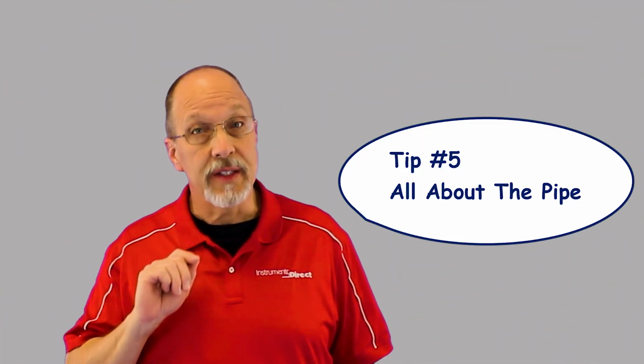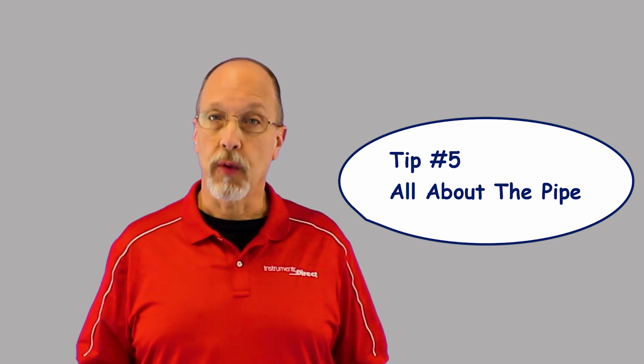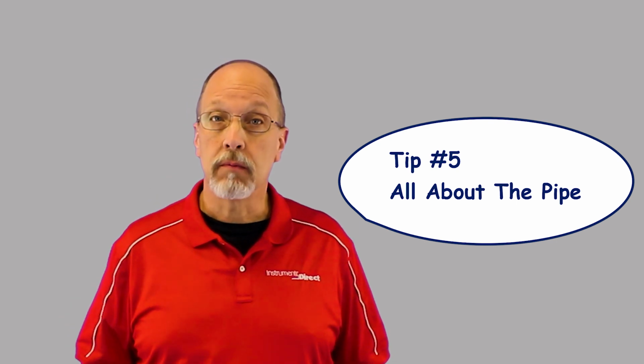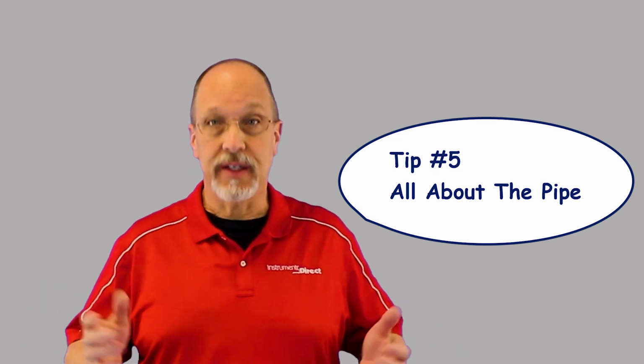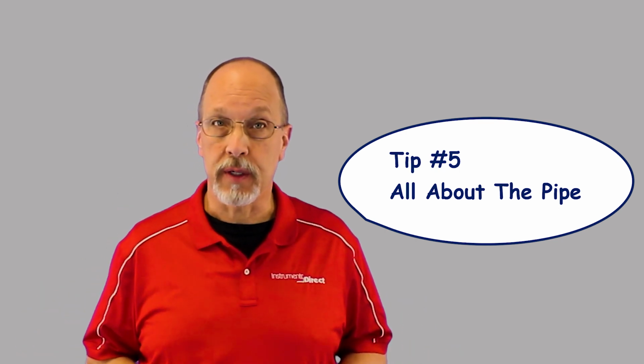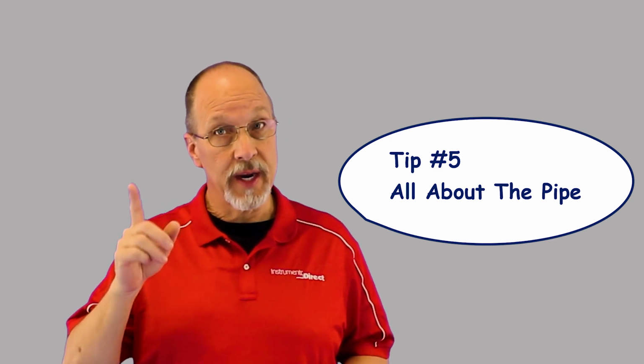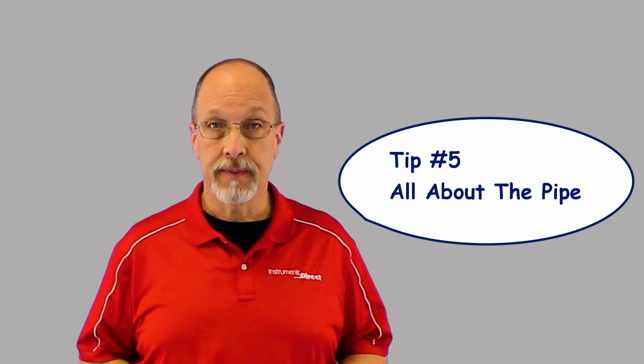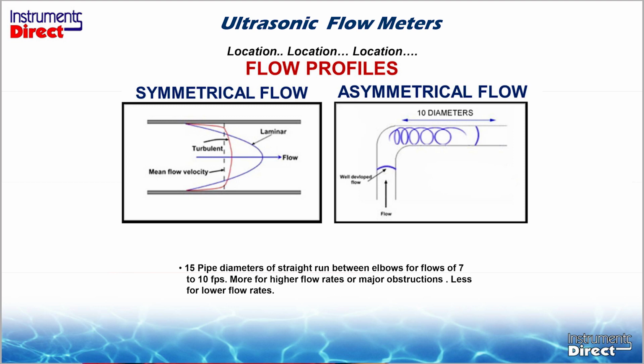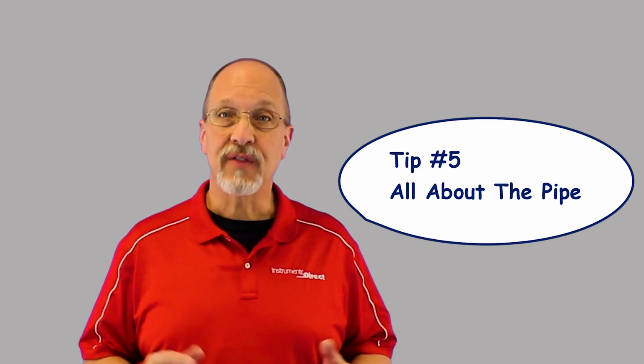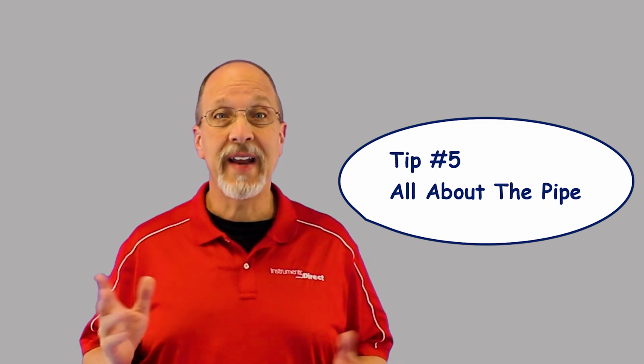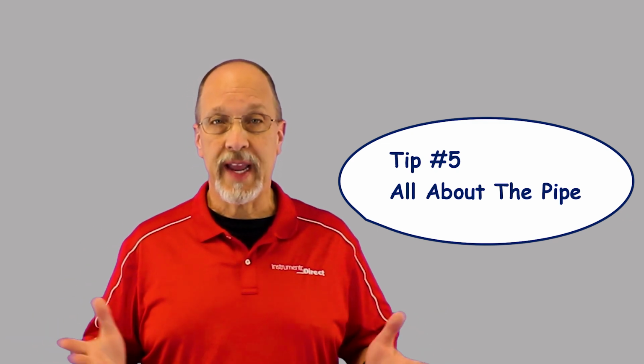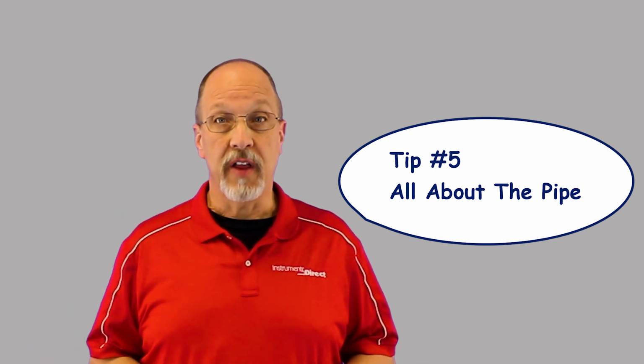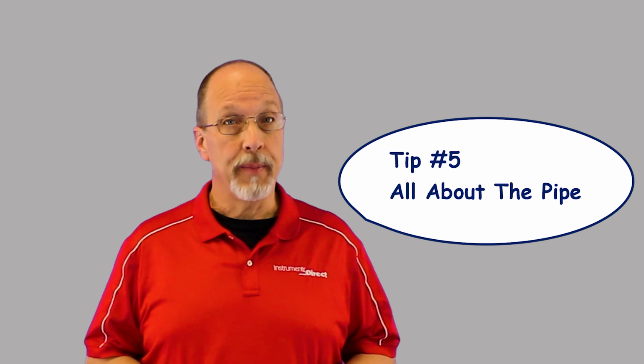Tip number 5, it's all about the pipe. All right, when it's time to install a flow meter and you have the insulation off and access to the pipe, you can now mount your transducer. But make sure you have enough straight run of pipe for optimum performance. For pumped flow, you will need the traditional 10 pipe diameters after an elbow and 5 pipe diameters before the next elbow. As for the pipe surface, all you need to do is remove any loose material or moisture. In most cases, a rag will do. But if you have an old rusty pipe, a wire brush might be a handy tool as well.